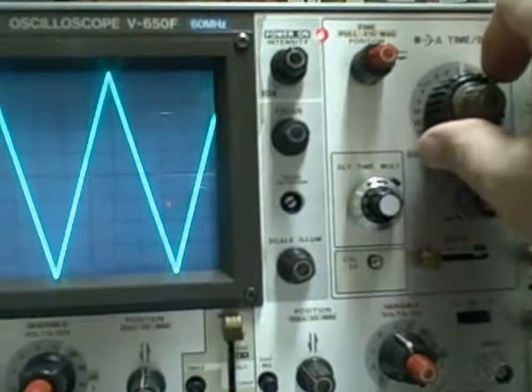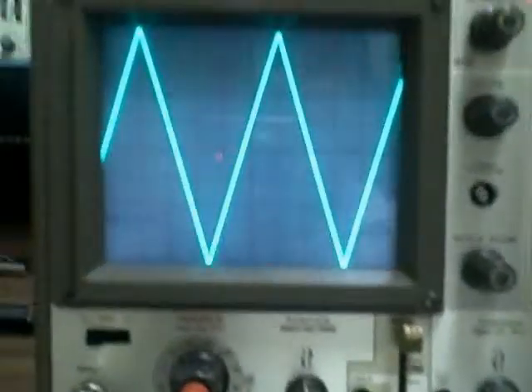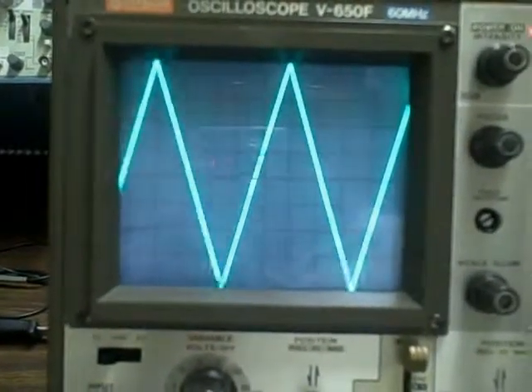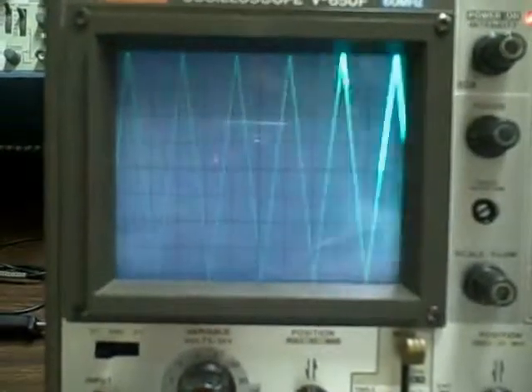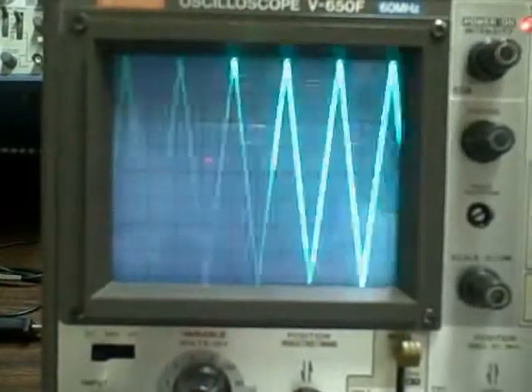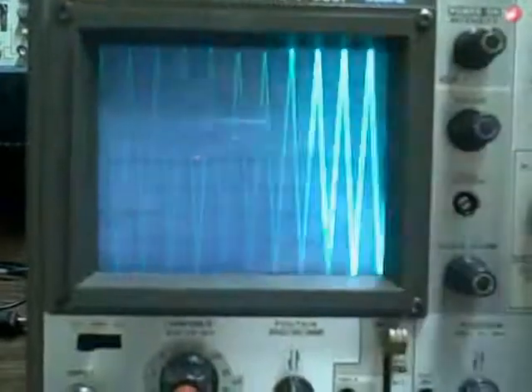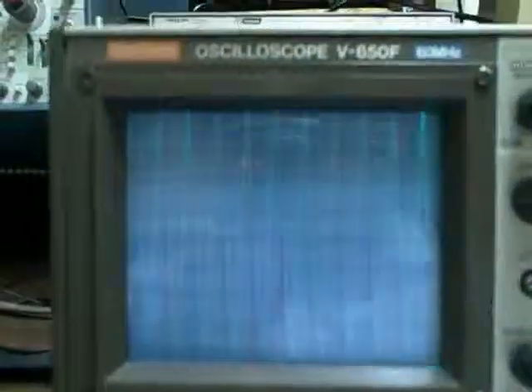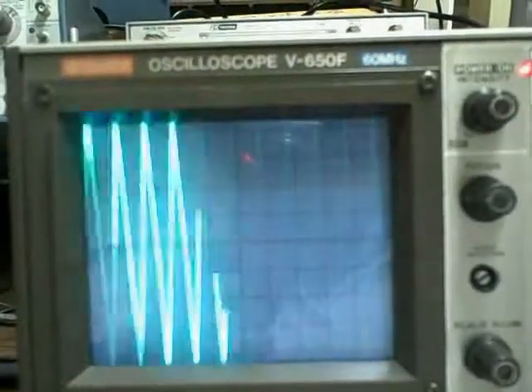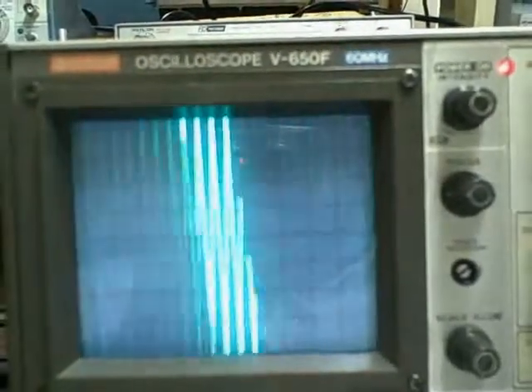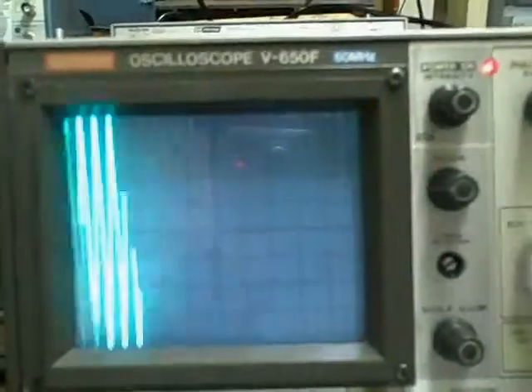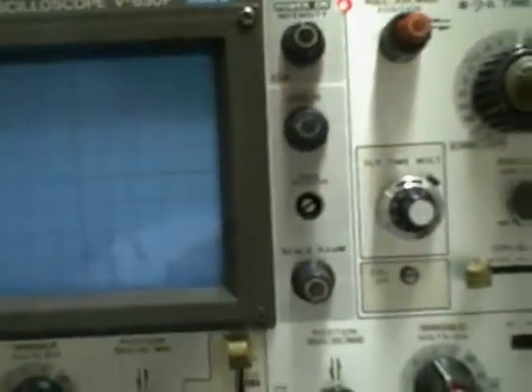And we'll, if we go to 2 milliseconds, we get 2 traces displayed. 5 milliseconds, we get 5. 10 milliseconds, we get 10 traces displayed across the screen. 20, we get 20, and you can tell there's 20 there. There's 2 in every division. But it does get hard to tell now at this point. And 50 would be relatively impossible. Because we don't have enough persistence in the phosphor to hold the image long enough for you to see what's there.